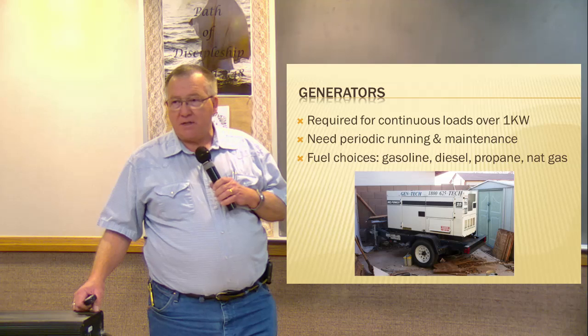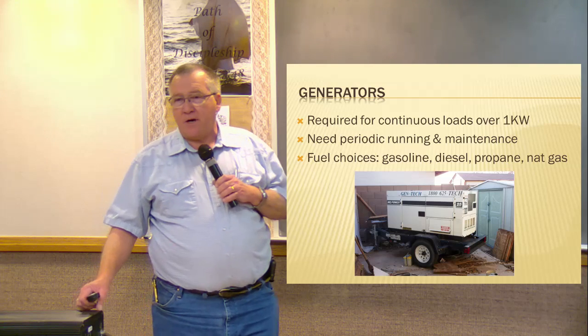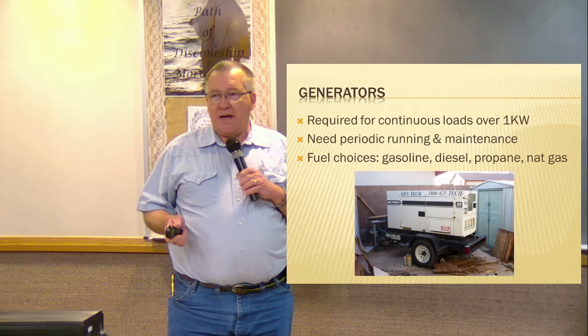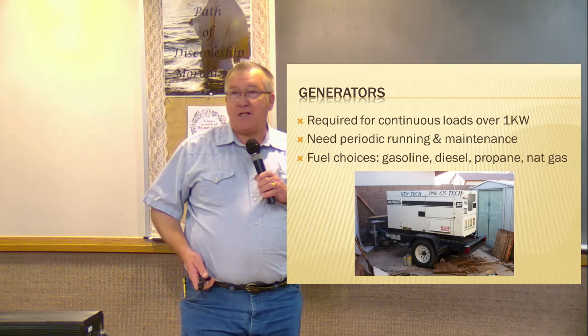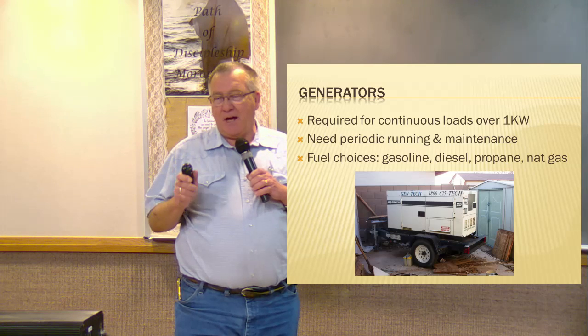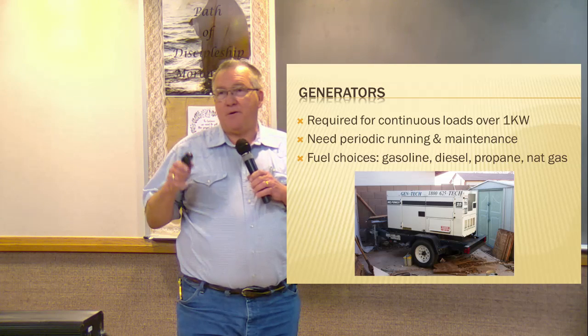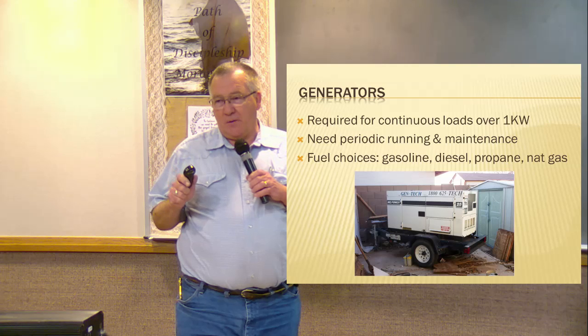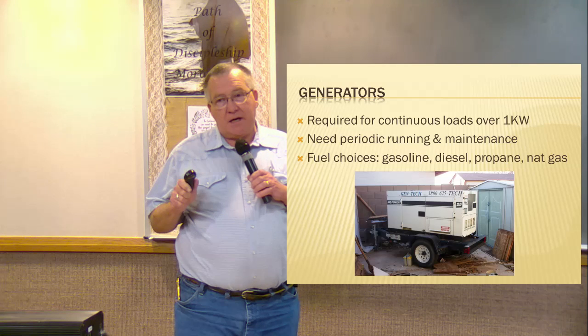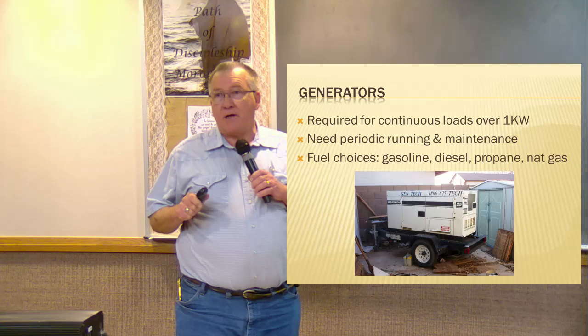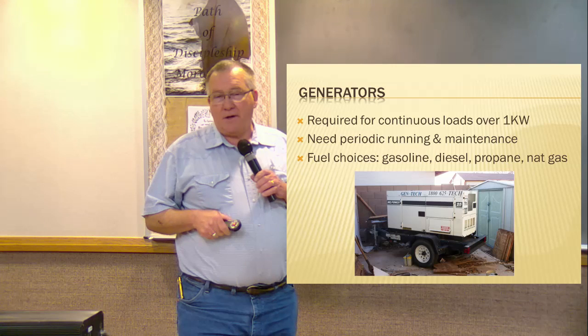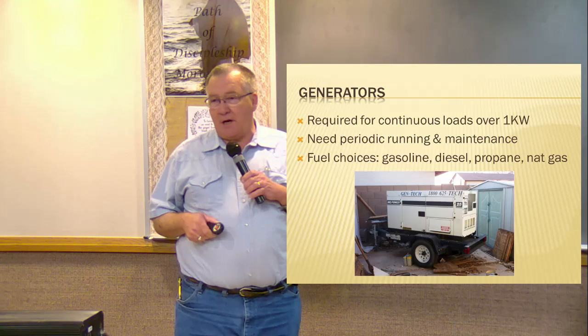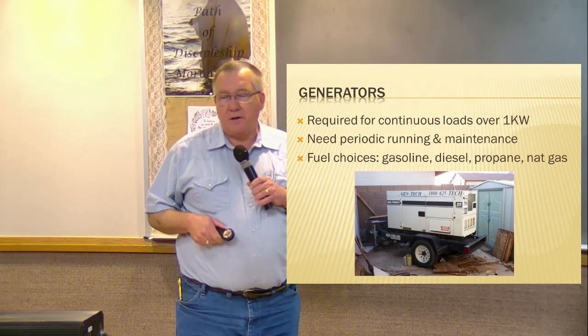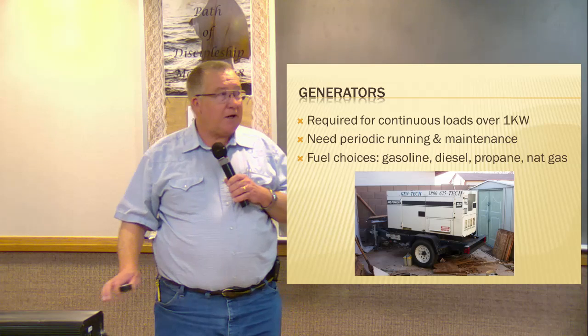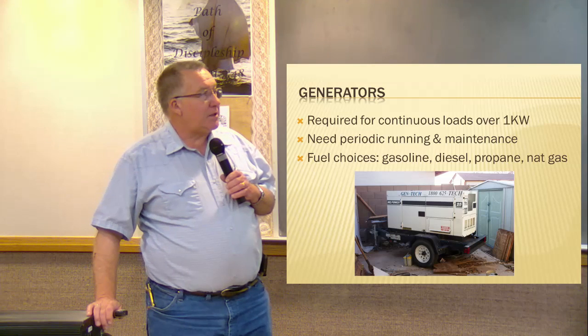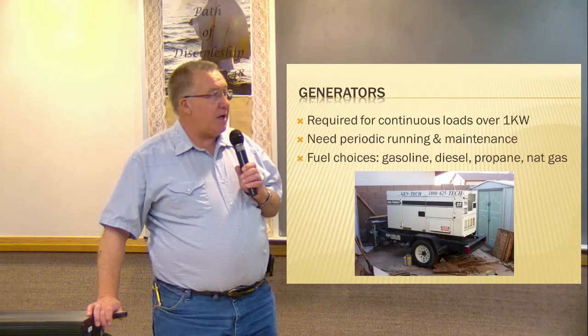Maintenance is, number one, running it periodically - start it up once a month, put a load on it, let it run for 20 minutes. They like that, it's healthy for them, and it lets you know it's going to be reliable and run. If you aren't going to run it for a long period of time, and it runs on gasoline, you've got to make sure you run it completely out of fuel. Otherwise your fuel system can plug up and it may not start, plus there are spark plug issues and everything else involved. So generators do need maintenance.